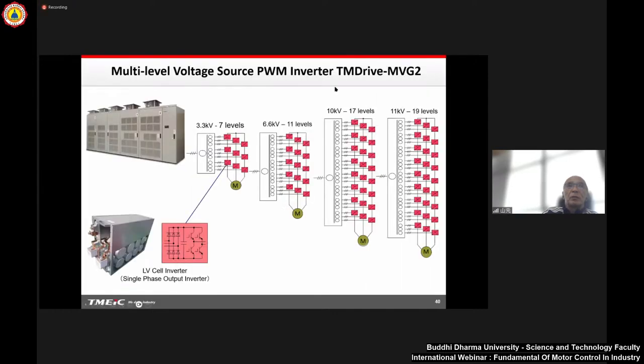Multi-level voltage source PWM inverters of TMEIC, we call TM drive MVG2. We have 3 kV, 6 kV, 10 kV, and 11 kV versions. As I explained earlier, the number of cells connected in series determines the output voltage, depending on the number of inverter cell units connected in series. So 3 kV is 7 level drive with 3 units in series, 6.6 kV with 5 units in series, 10 kV with 8 units in series, and 11 kV with maybe 9 units in series, to increase output voltage.